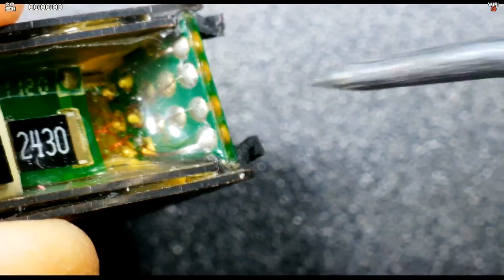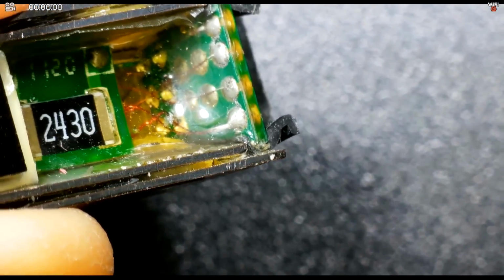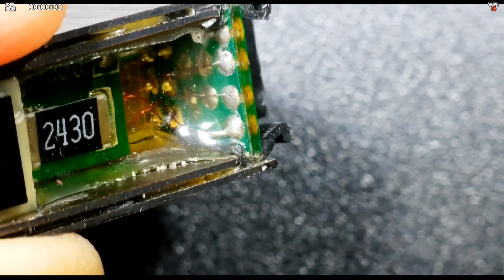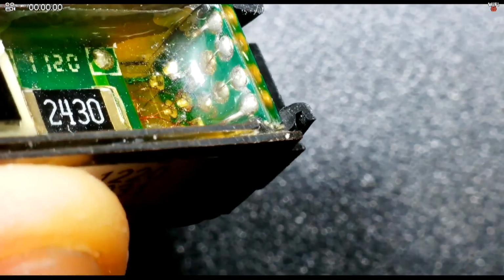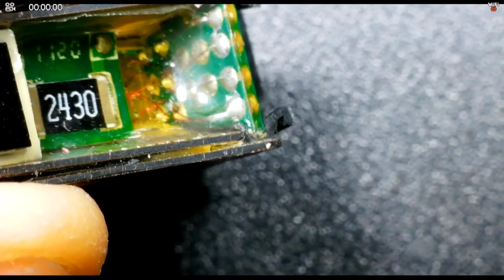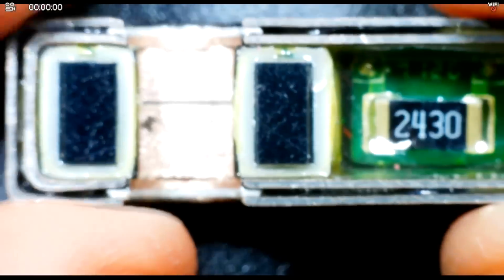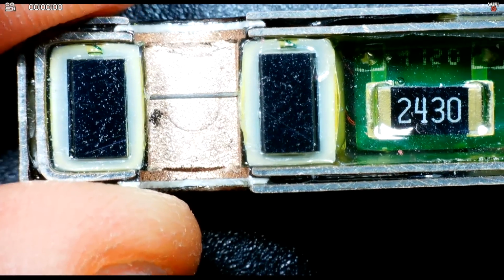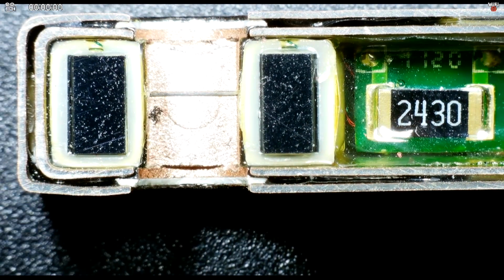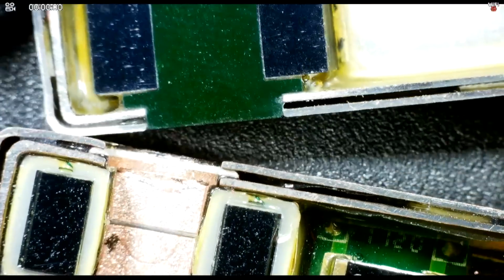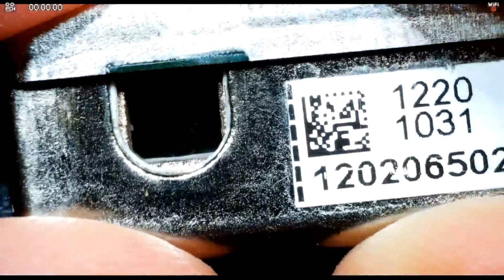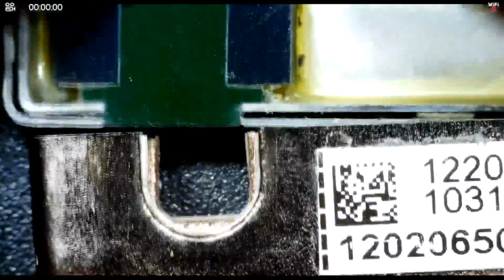Now if one of these cables is bad, I would be really surprised because this thing cannot move anyway because it's all potted down. But nonetheless, we should be able to make some comparative measurements. So here are the two transformer heads that you can see, and there's the opposite part of it. So this is the top of the probe head. You can see this doesn't have any electronics in it, but these two mate on top of each other like so. And when they're closed, you basically have a complete transformer.